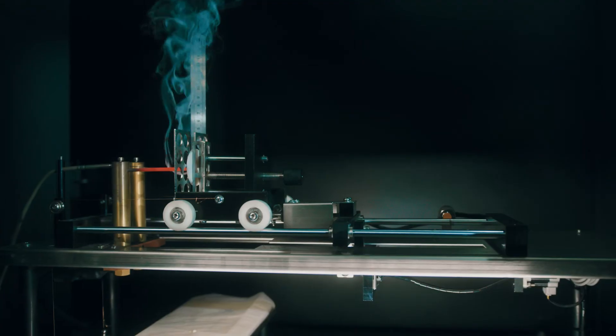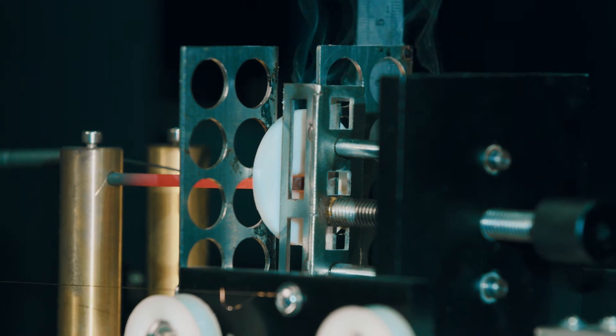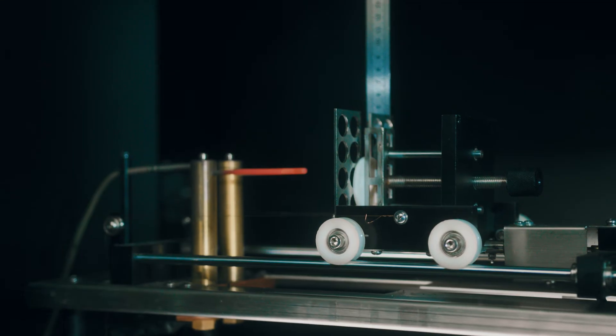If the flames or the glowing combustion of the test specimen extinguish within 30 seconds after the glow wire is removed and the tissue paper under the test specimen does not ignite.